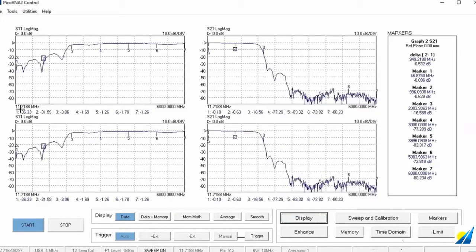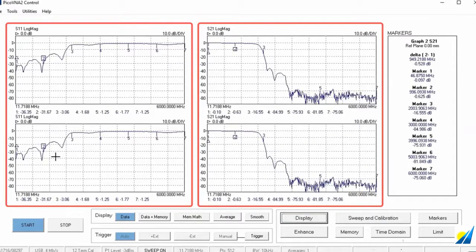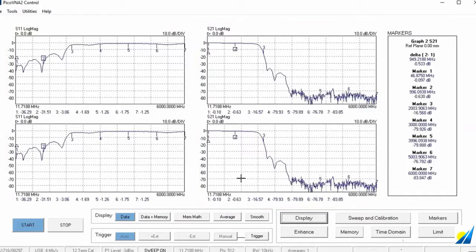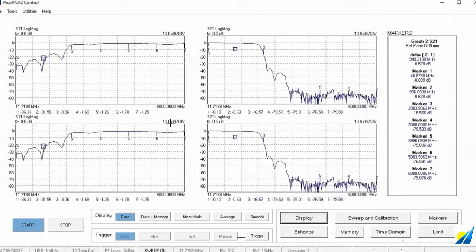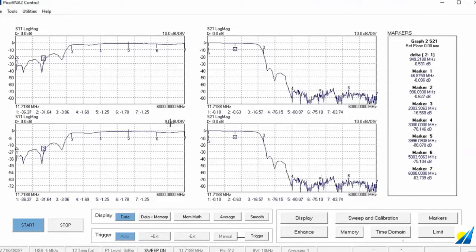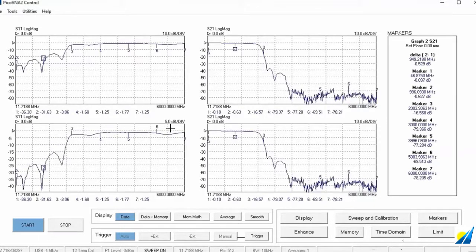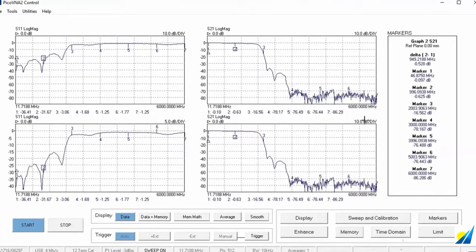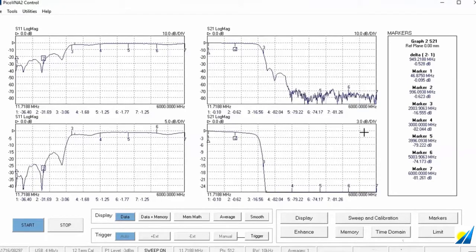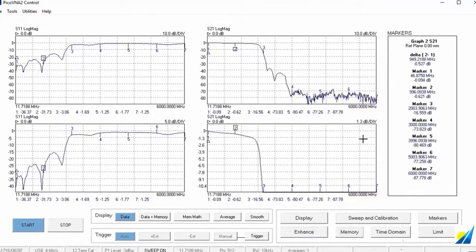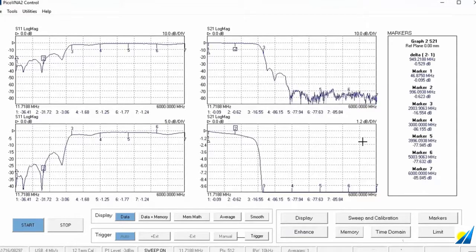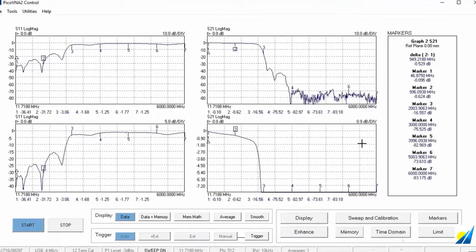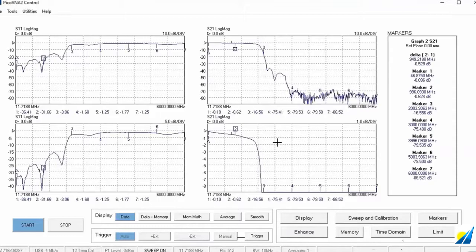So now I've got two identical plots on the left, two identical plots on the right. What's the point of that? Well, let's increase the sensitivity of this one. We'll pull that one down to five. We can pull this one down here. So basically what we're saying here is any one of the channels can display any one of the parameters. And in fact, they can all display the same parameter if we like.